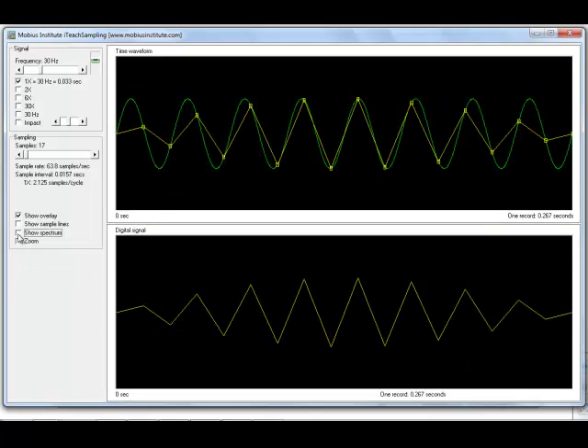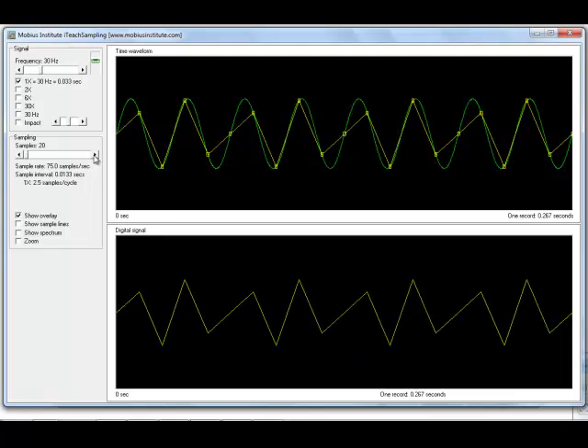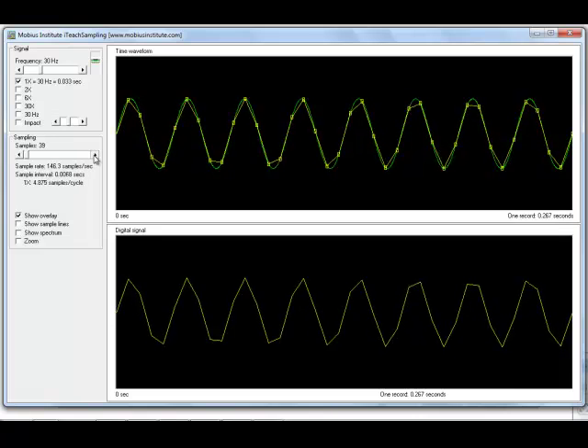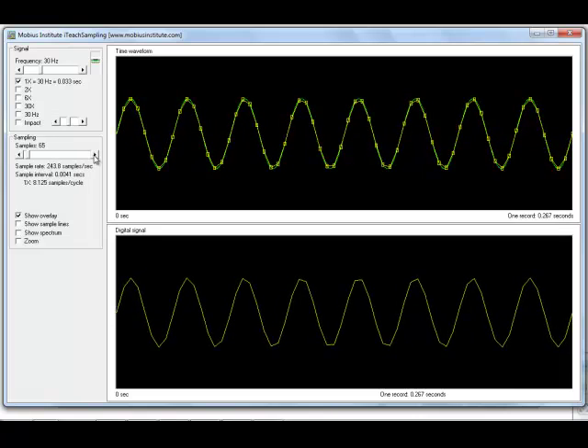The fact is we have to sample more than twice per cycle. From a time waveform analysis point of view, this is terrible — we can't really see what's going on. We'd like to have the sample rate up higher. If I lean on this for a while, now I can see all of these samples on each cycle, and my digital version of the signal starts to look a lot more like the green analog version.